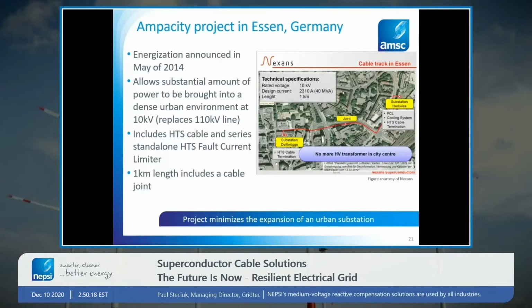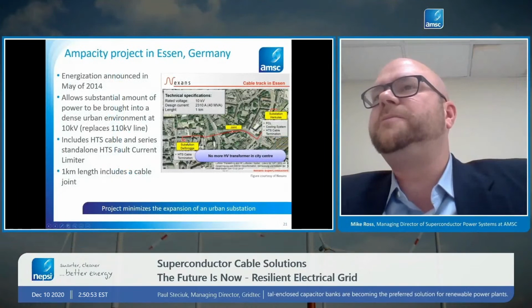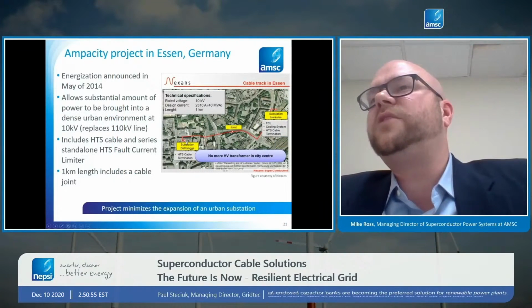So what they did instead is they put the new transformer out in the suburbs where you had plenty of room, and then brought the power in using a 10 kV superconductor cable, 2300 amps, 40 MVA, into the substation. And now they were able to increase the capacity of the substation by 40 MVA just by adding in a new switchgear cubicle and a new termination for the superconductor cable. So much smaller. So they were able to avoid expanding an underground urban substation because of this technology. And that's why this is so attractive.